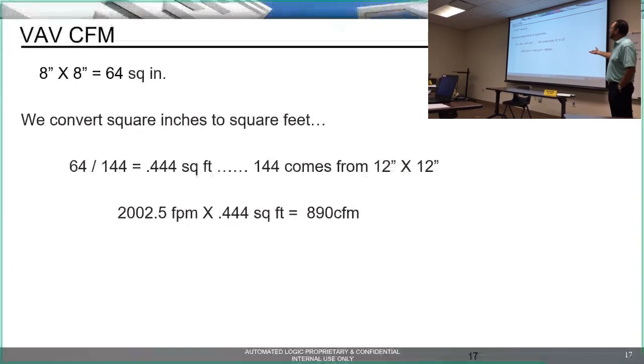So, again, just math. A while ago I said if we know the area and the velocity in feet per minute, then we can calculate the CFM, cubic feet per minute. Just simple math: take an 8x8 duct, multiply 8 times 8, that's 64. Then we have to convert inches to square feet, so you divide 64 by 144.